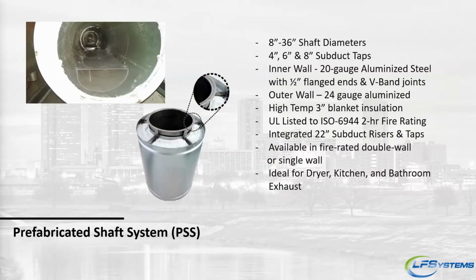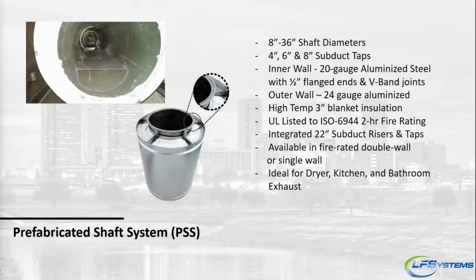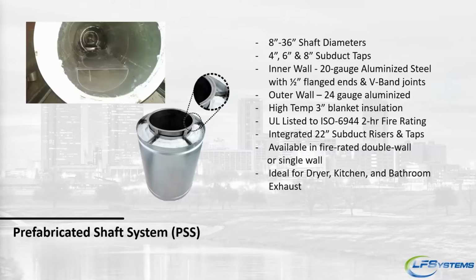This is a round shaft with integral subducts as an option. So we go 8-inch to 36-inch round with 4, 6, or 8-inch taps. Inner wall is 20-gauge galvanized or 20-gauge aluminized steel with a 1/2-inch flange, and the outer wall is 24 gauge. We provide a 3-inch insulation blanket straight from the factory. So it is prepackaged, wrapped from the factory, and it is UL listed to ISO 6944 for the 2-hour fire rating. So this is now not only your ductwork, but it's also the shaft itself.